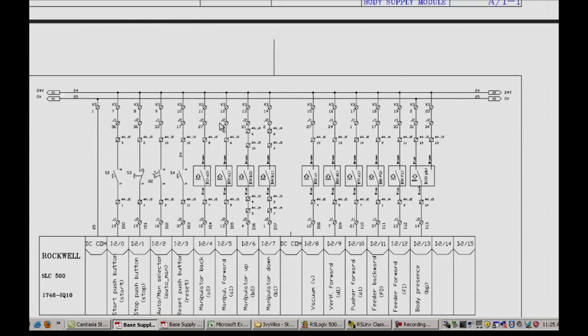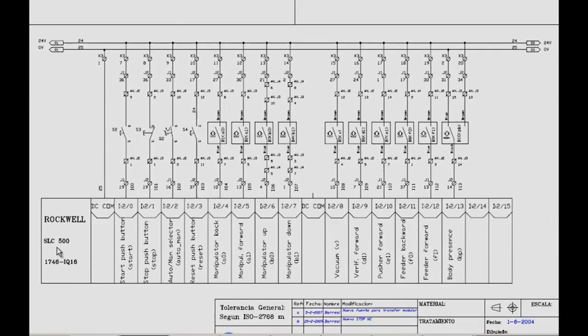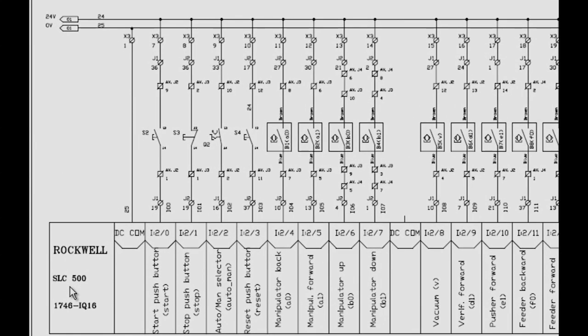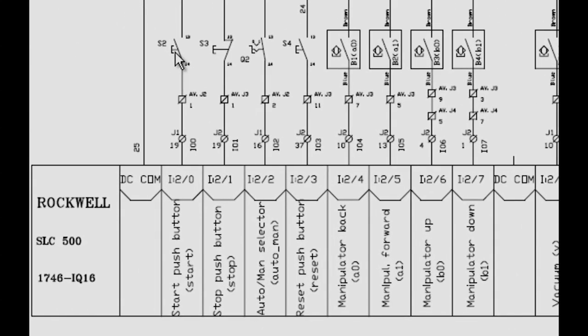The next page is really important — this is our input page. We can see that we've got 24-volt inputs being connected to this station. We've got I:2/0, which is our start push button, indicated by the IEC symbol for a push button. And the next one is our stop push button. We know that one is wired normally closed, so we'll have to take that into consideration when we write our program.